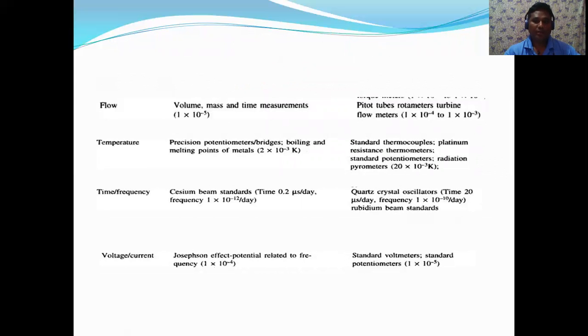The next parameter is flow. The primary standard is volume, mass, and time measurement, at 1 × 10^-5. The secondary and working standard range is 1 × 10^-4 to 1 × 10^-3. The next parameter is temperature. The primary standard is precision potentiometers and the boiling and melting points of metals, at 2 × 10^-3 Kelvin. The secondary and working standard is 20 × 10^-3 Kelvin.